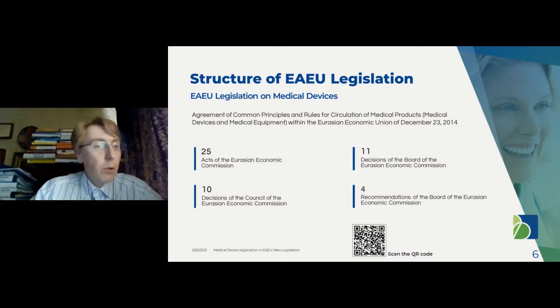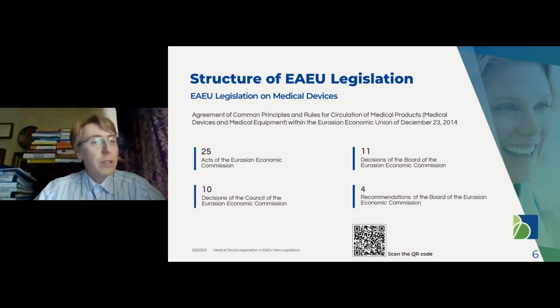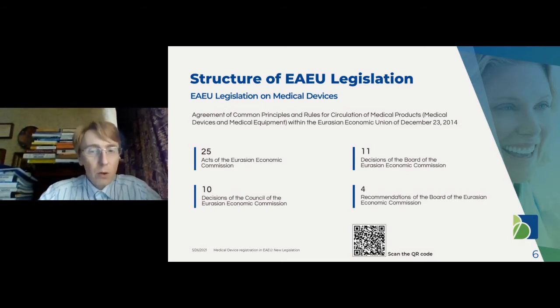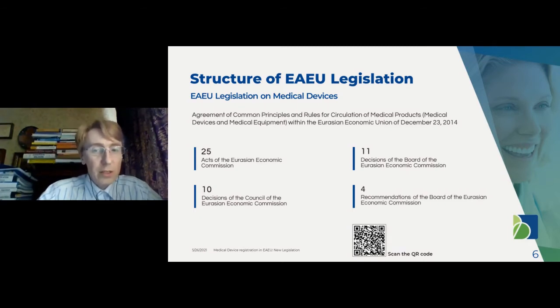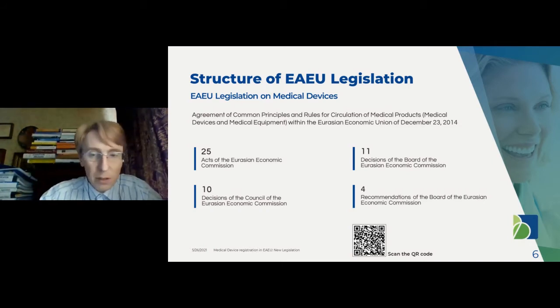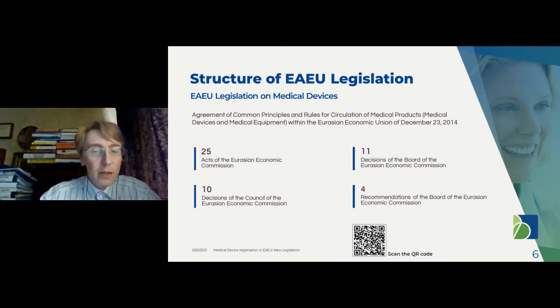The main problem here is the following: MDR includes 123 articles, 17 annexes, and is about a 175-page document — one big document with comprehensive information on medical device regulation. Eurasian Union regulations consist of 50 separate documents. There is no problem printing and binding them in one folder, but sometimes we find light discrepancies in approach and rules, and also duplicates of terminology where definitions are slightly different.